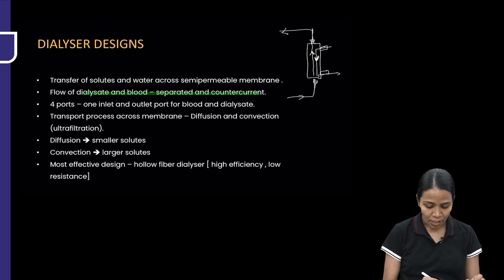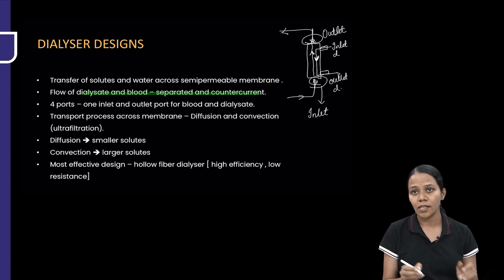It has four ports. One is an inlet port for the blood, and this is the outlet port for the blood. This is the inlet port for the dialysate, and this is the outlet port for the dialysate.